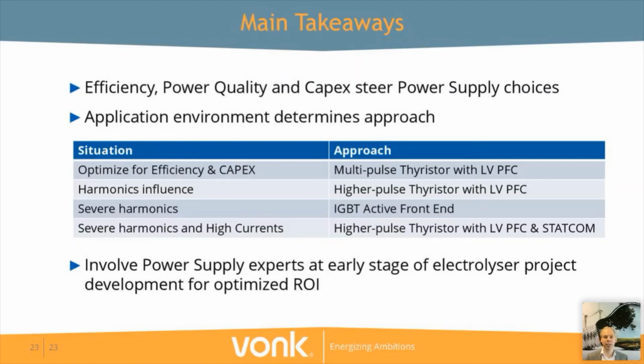If you have a situation in which there is severe harmonics, an IGBT active front end has superior power quality performance and solves most of your problem. However, if you have severe harmonics and high currents in place, the IGBT active front end becomes a very expensive solution. Therefore, in that case, we would suggest to use a higher pulse thyristor solution with low voltage power factor compensation, as well as STATCOM at medium voltage.